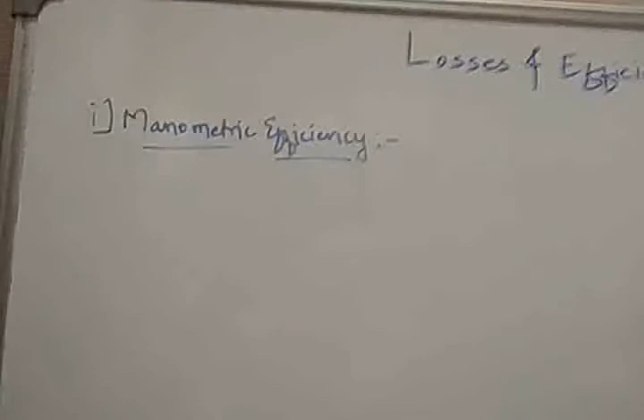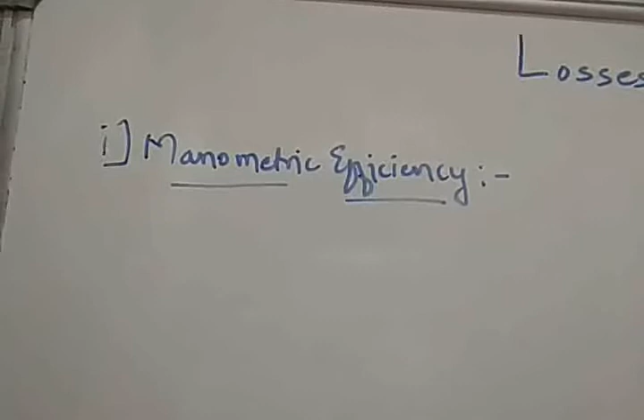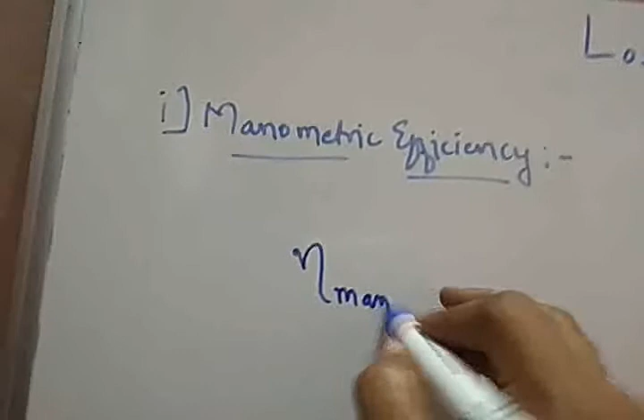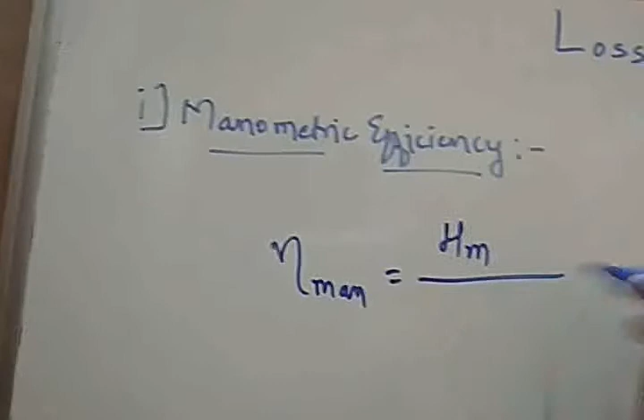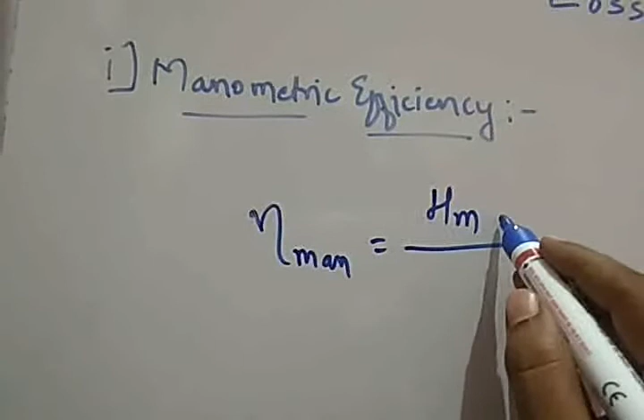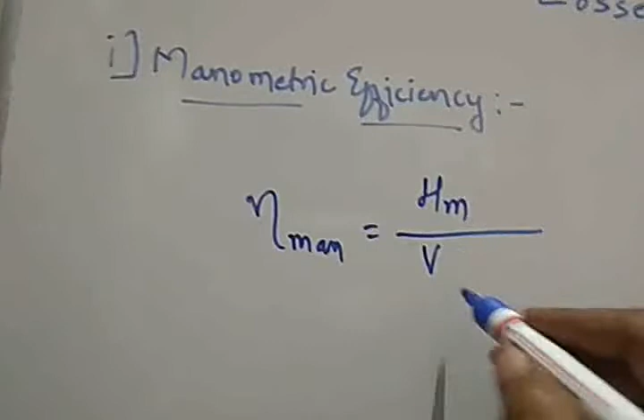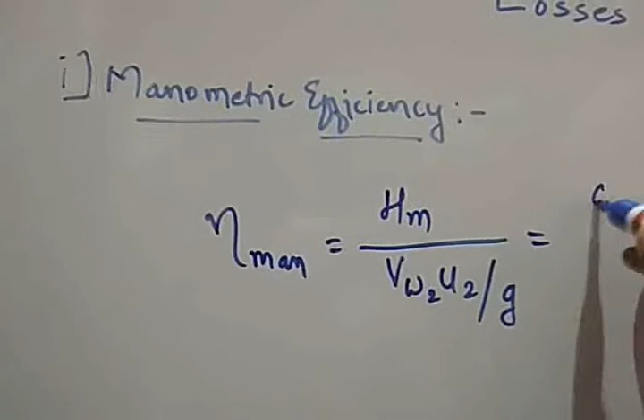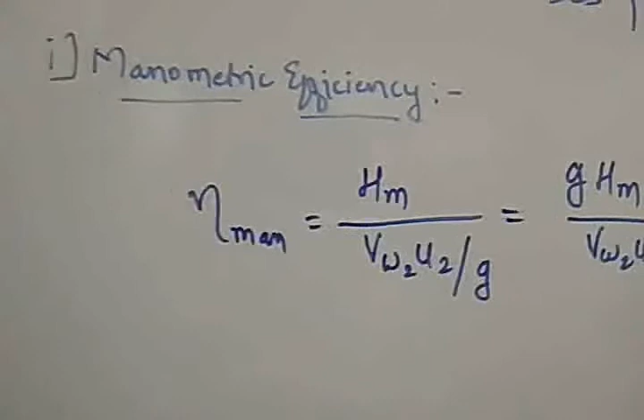The first efficiency is the manometric efficiency. The manometric efficiency is the ratio of the manometric head developed by the pump to the head imparted by the impeller to the liquid. Hm is the manometric head, and the head imparted by the impeller to the liquid is given by Vw2 U2 upon g. So I can write this as g Hm divided by Vw2 U2. Now we know that Hm is equal to Vw2 U2 by g minus losses in the pump.